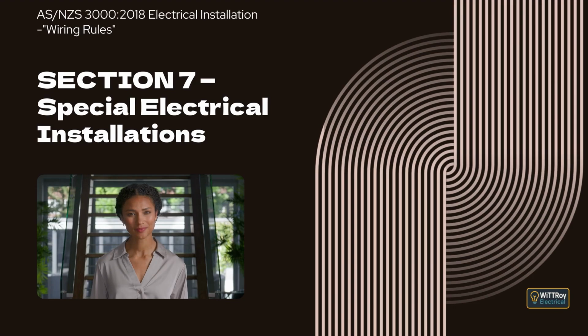Clause 7.5.3, Sources of supply to SELV and PELV systems. This clause explains that SELV and PELV systems must be supplied from approved sources. These include a safety isolating transformer complying with AS/NZS 61558, an independent source such as an engine-driven generator or battery, a separated source such as a motor generator set with electrically separate windings, or certain electronic devices designed so that output voltage cannot exceed extra low voltage under fault conditions.